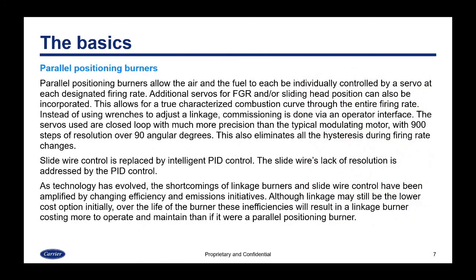Parallel positioning burners allow the air and the fuel to each be individually controlled by a servo at each designated firing rate. Additional servos can be added for FGR, flue gas recirculation, or a sliding head position can also be incorporated. And this allows for a true characterized combustion curve through the entire firing rate.